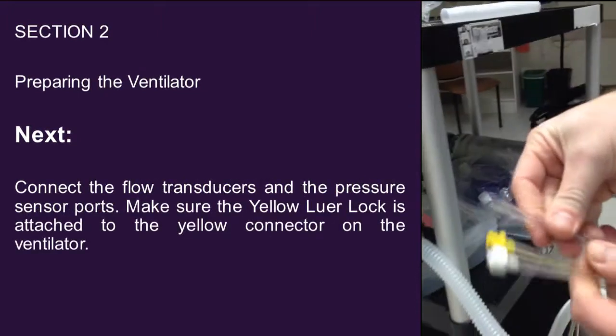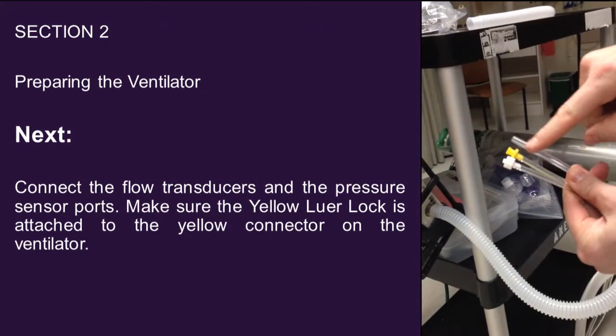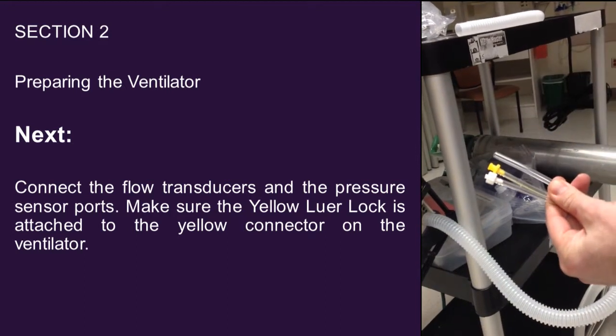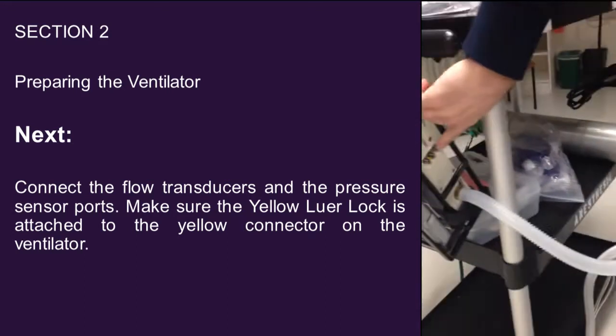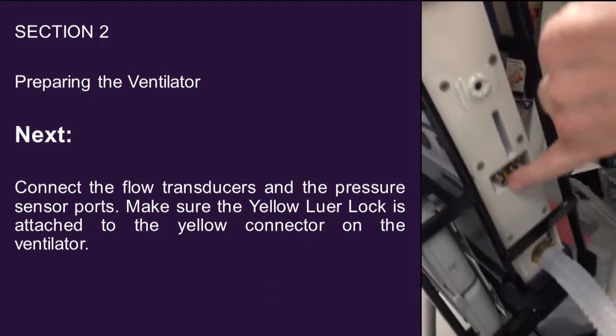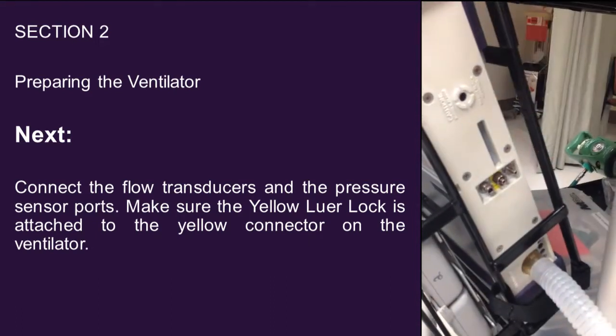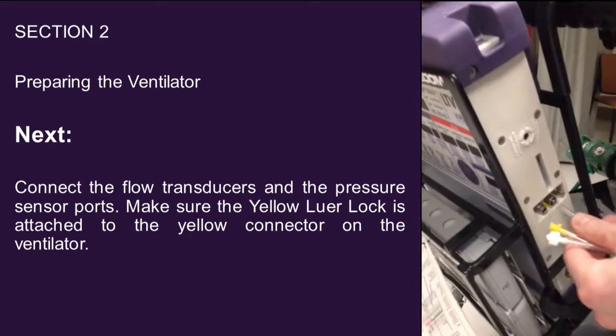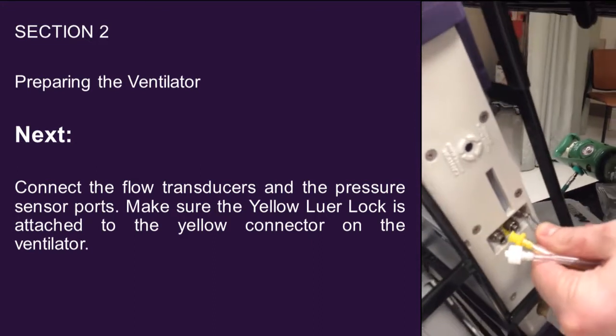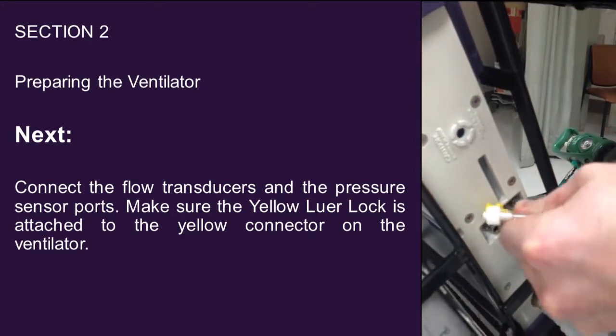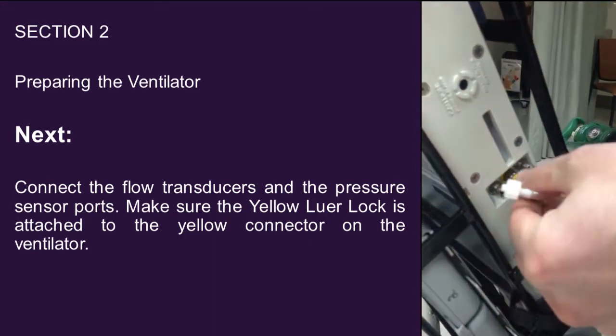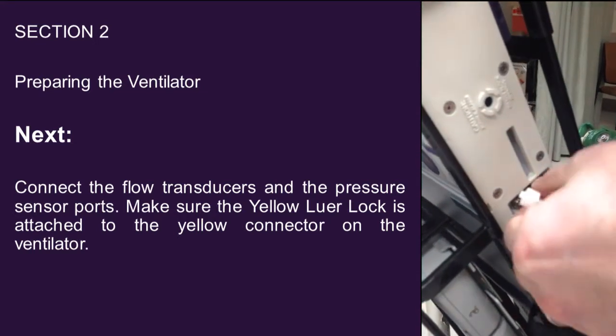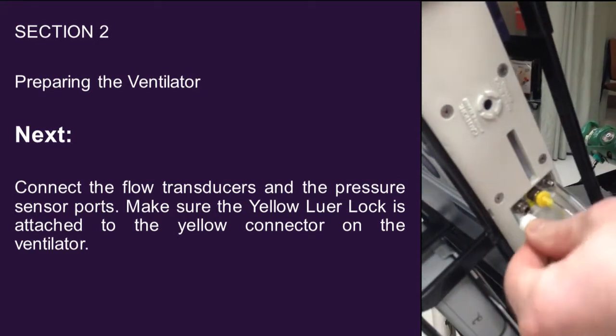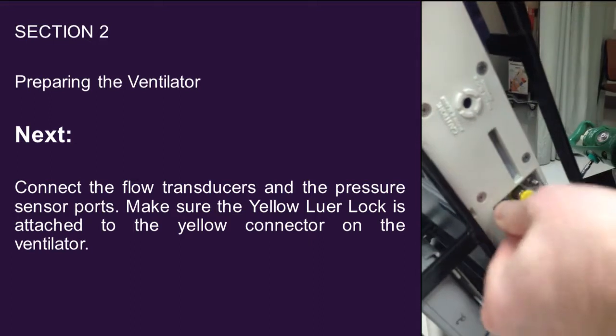You'll then see that you have three connections here, a white, a yellow, and one with nothing. And actually, if you look on the ventilator right here, flow transducers and pressure sensors. And so then those just get hooked up as follows. The one with no connector goes on here. Yellow, which has a yellow luer lock, goes to yellow luer lock. White luer lock goes to white luer lock.